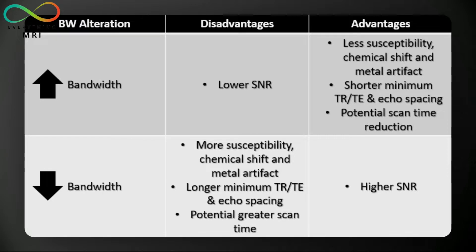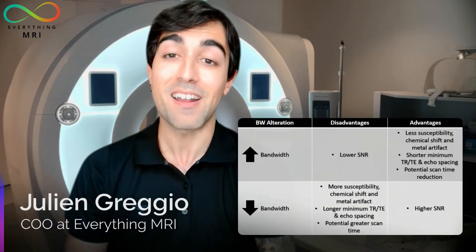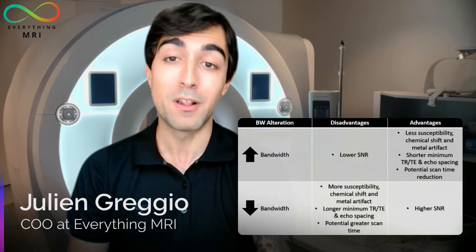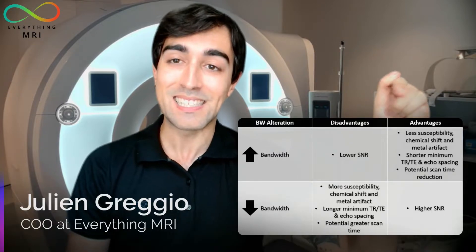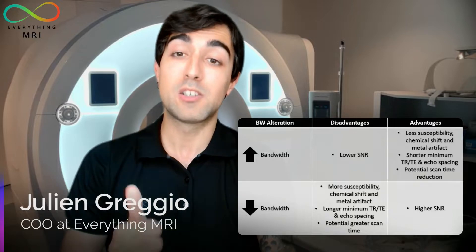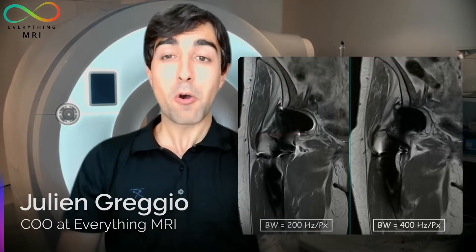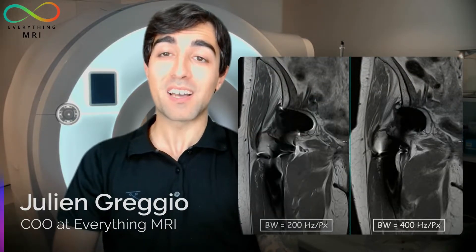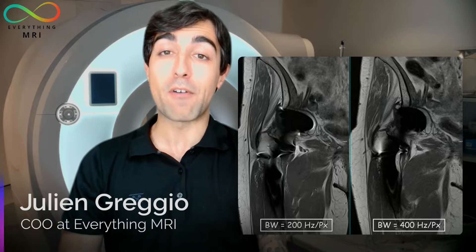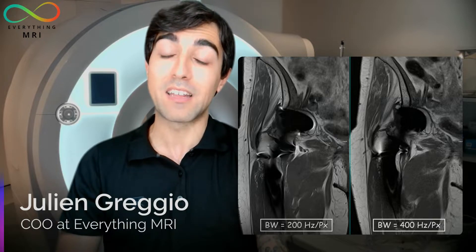Regardless of this, a common action we perform as MR technologists is bringing the bandwidth up. Someone might think: why would we deliberately reduce our SNR? The reason is, as shown in this table, increasing the received bandwidth comes with the major benefit of a reduction of susceptibility, chemical shift, and especially metal artifacts. We mentioned in the MARS video that boosting this parameter will have a major impact on reducing in-plane distortions on images potentially affected by metal implants.